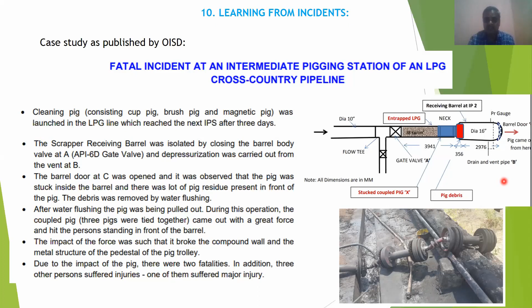Learnings from incidents. The learnings are as follows. Health assessment of the LPG pipeline must be carried out since the pig residue indicated considerable iron content of 90.99%, indicating metal loss due to internal corrosion. See, because of the internal corrosion, there will be metal loss from inside. Nobody can see it from outside. Pigging must be done regularly and the residue must be analyzed to ascertain the health of the pipelines. An additional vent and drain point with pressure gauge shall be provided in the neck portion of the barrel to drain the hydrocarbon. That is most important.